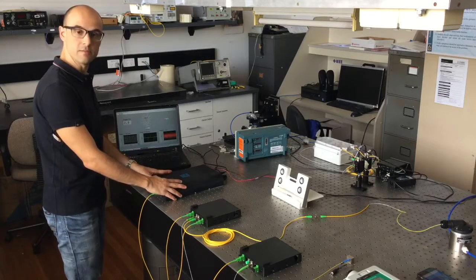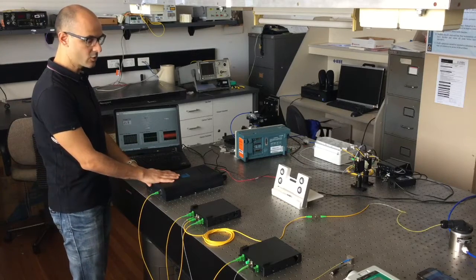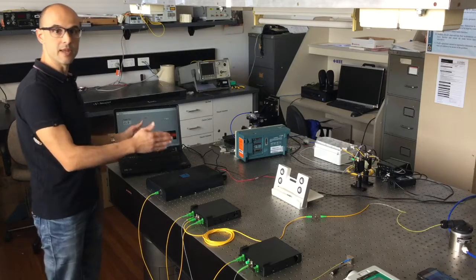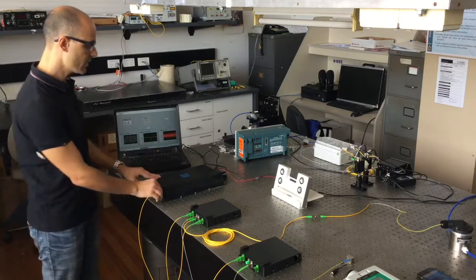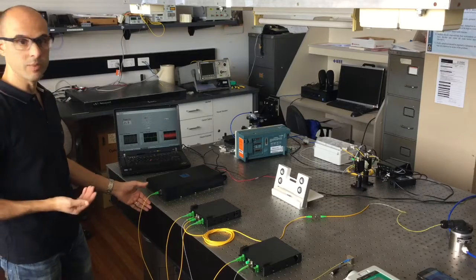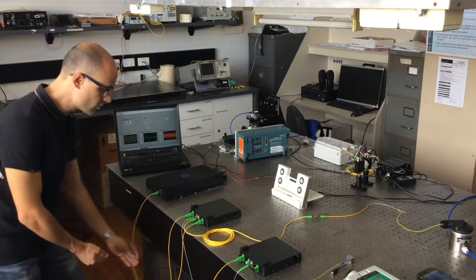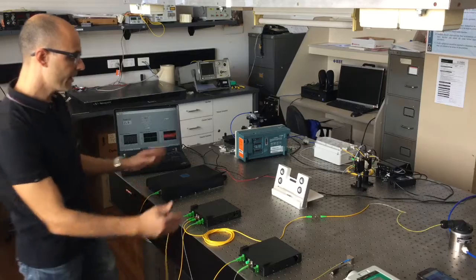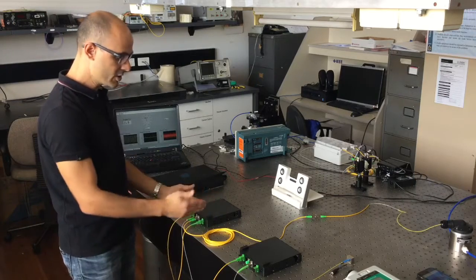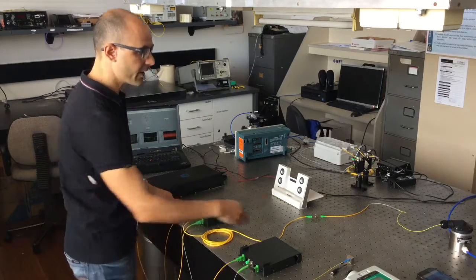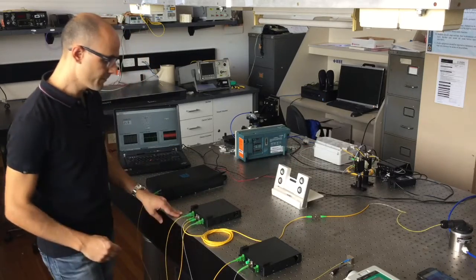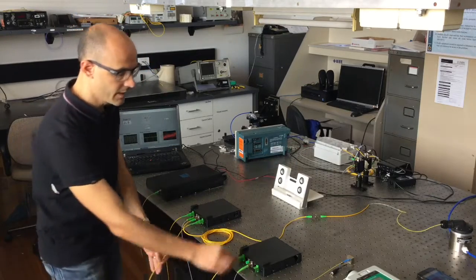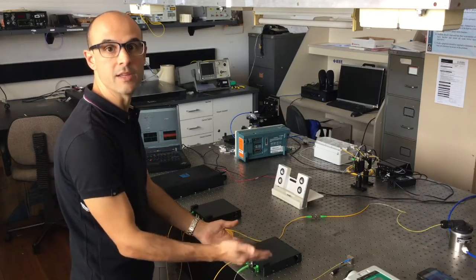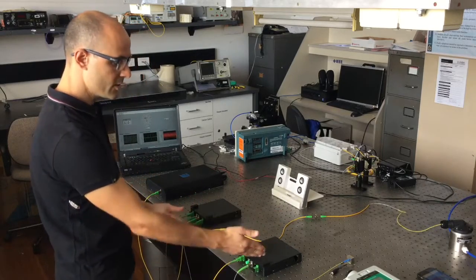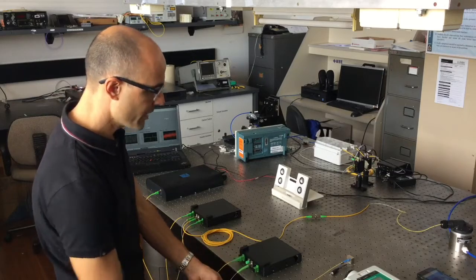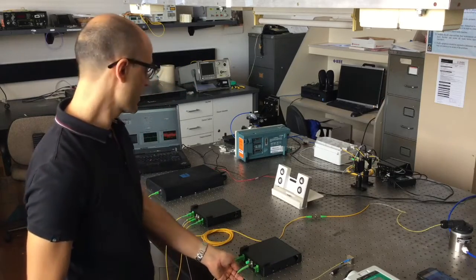We have a headend box here, which contains a light source. It's a broadband light source that contains many wavelengths, or channels, as we call them in wavelength division multiplexing terminology. All the channels go to the backbone fiber, and at the add-drop filters, some of the channels are branched off, and they are directed to the corresponding sensor. The rest of the channels go through, and then we can daisy chain as many add-drop filters as we want. In this case, we daisy chain another add-drop filter, and we branch off to read another sensor here.